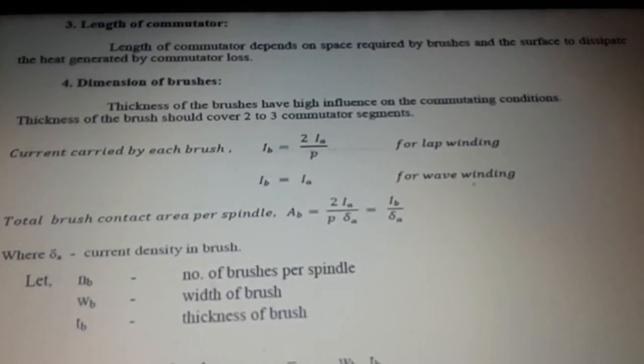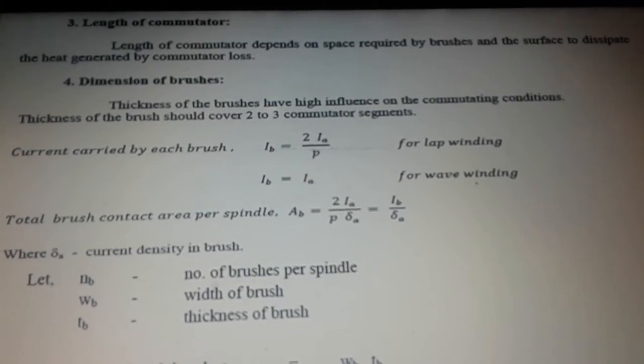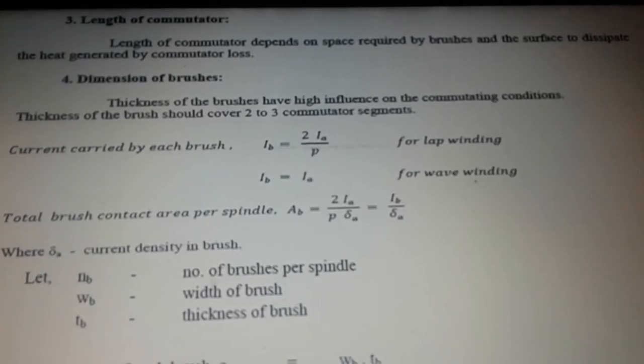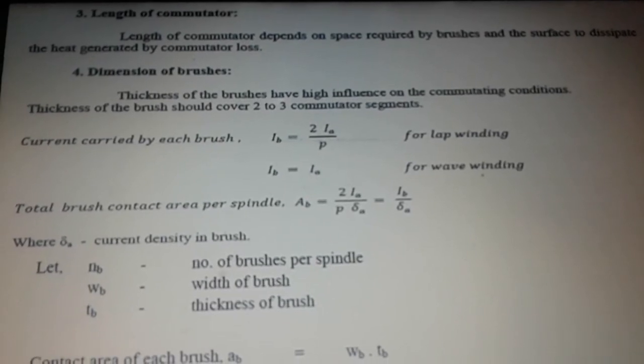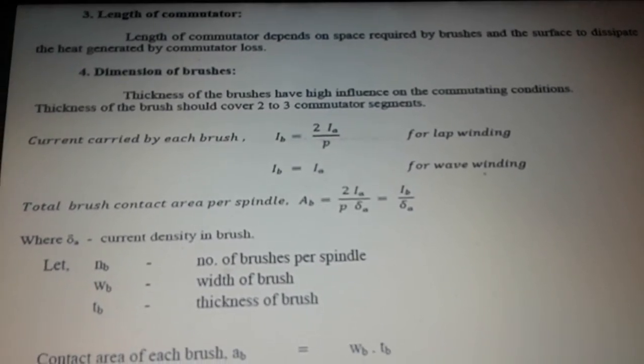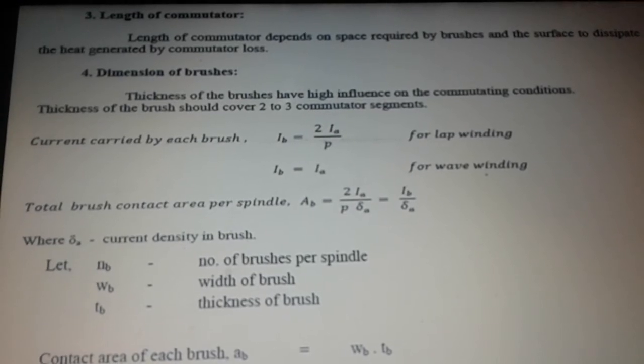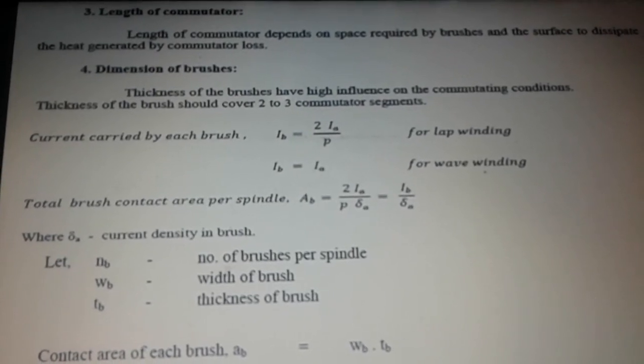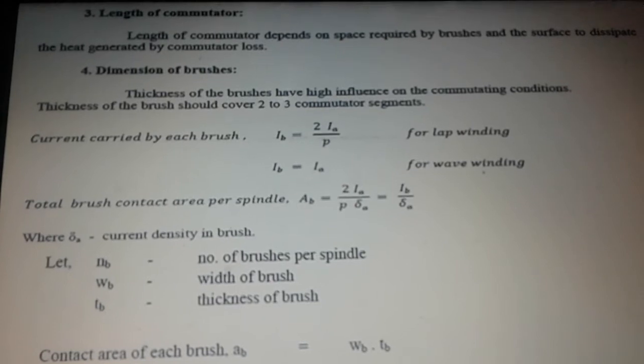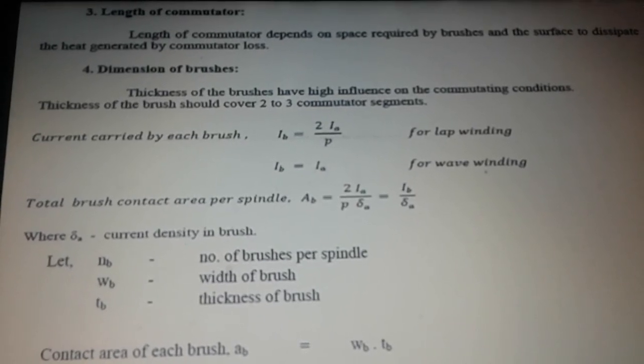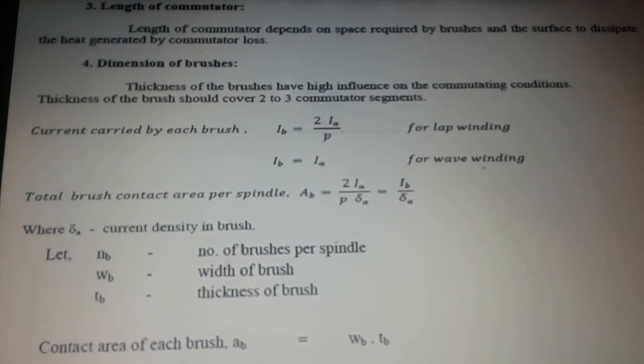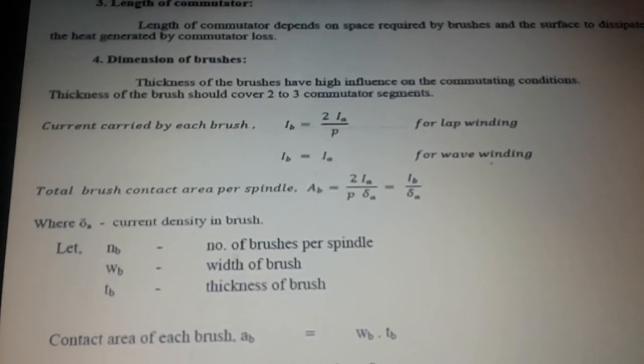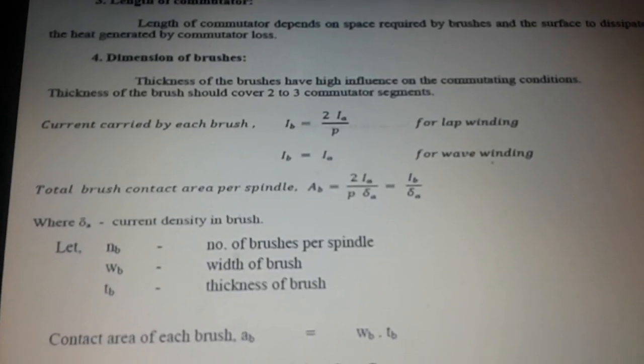Current carried by each brush is 2IA divided by P for lap winding, and for wave winding IB equals IA. The total brush contact area per spindle is 2IA by P delta A, which is IB divided by delta, where delta is the current density in the brush.